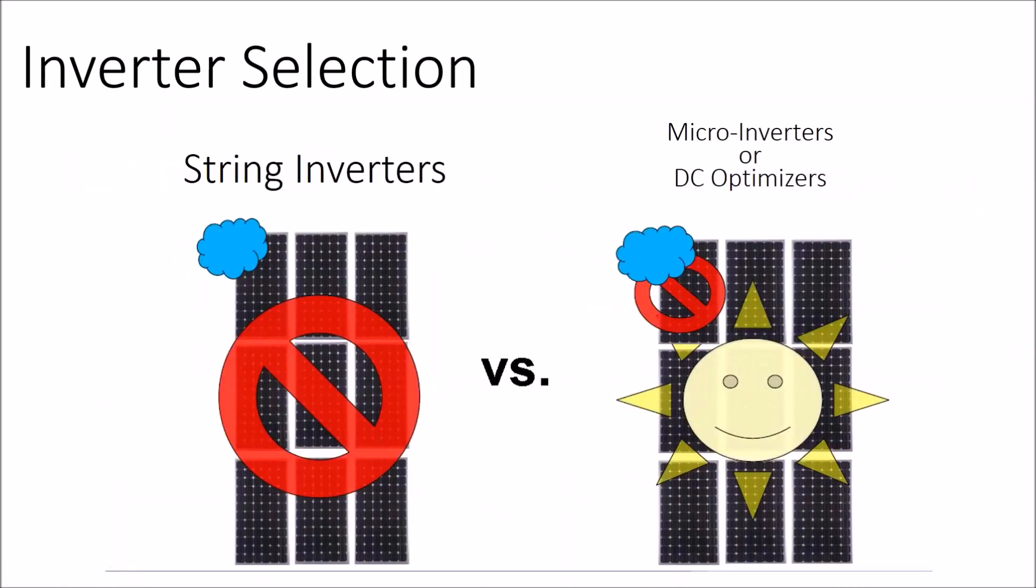The reason is, remember old-school string inverters, the littlest bit of shade would wreak havoc on the entire system. So microinverters and DC optimizers nowadays serve a fire protection function, but they used to just serve a performance boost in shaded environments. Nowadays, the string inverters are more shade tolerant, so the shading arguments are still there but not as much as they have been in years past.